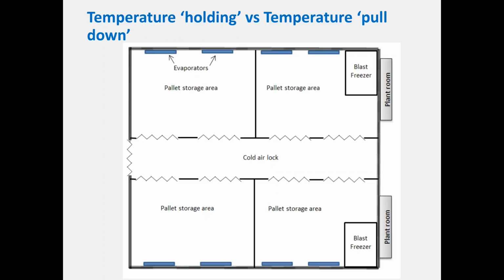Another distinction we need to make is between temperature holding and temperature pull down. So I've got a diagram, let's say it's a meat freezing works somewhere. Your temperature pull down is supposed to be done by your blast freezer. So they'll have a relatively small volume but with higher air velocities. And they may be continuous or they may be batch. But importantly, they'll want air to go around. If it's a carton freezer, they'll want each carton to be exposed to air on all sides. Once it's down to temperature, you'll take it out and you probably put it in a pallet with others and put them in the pallet storage area.